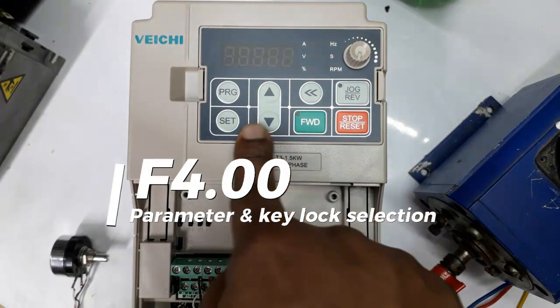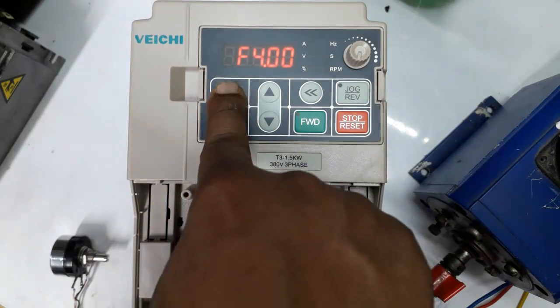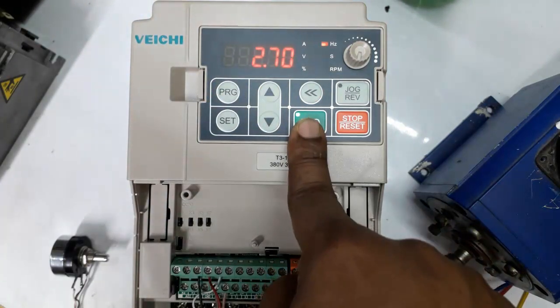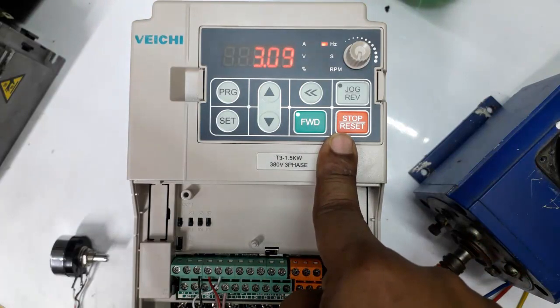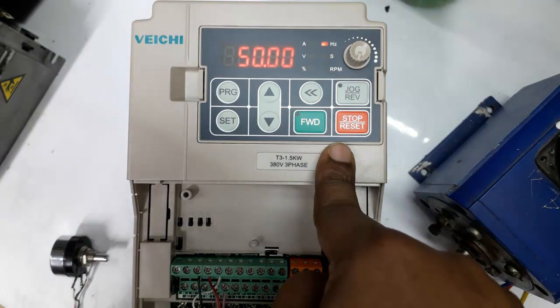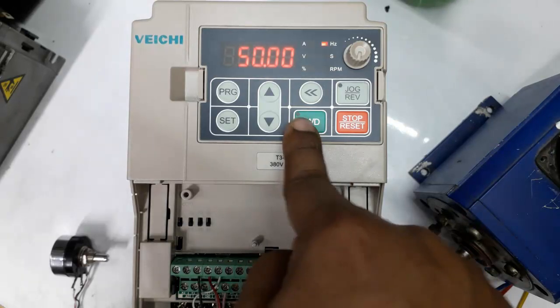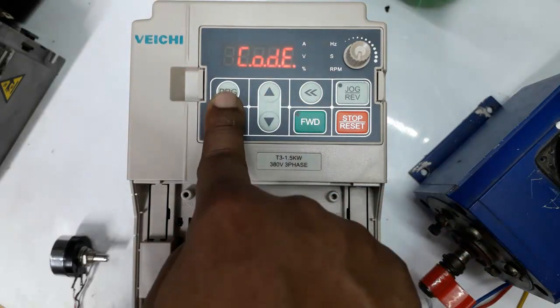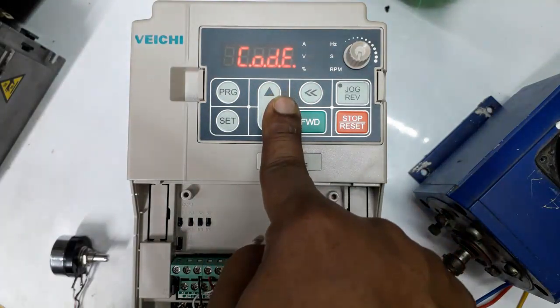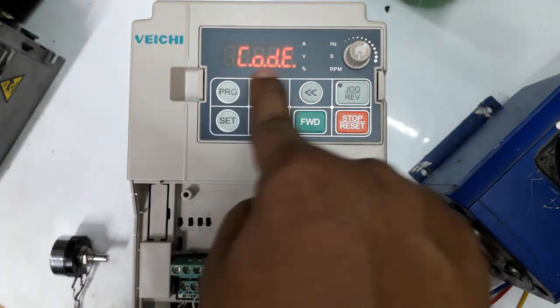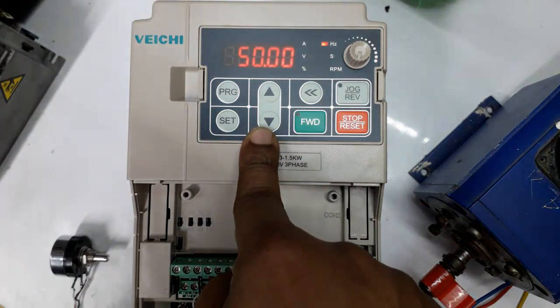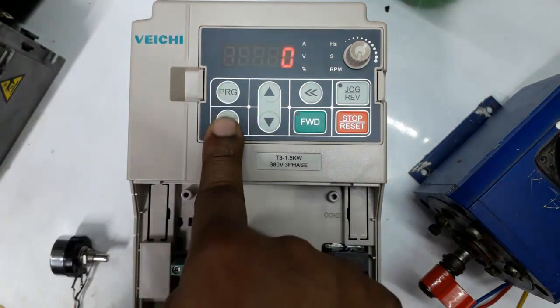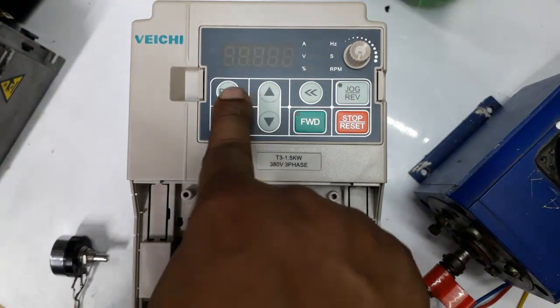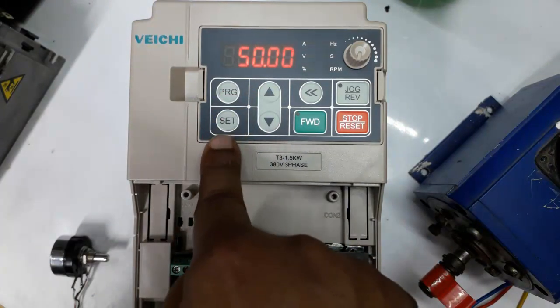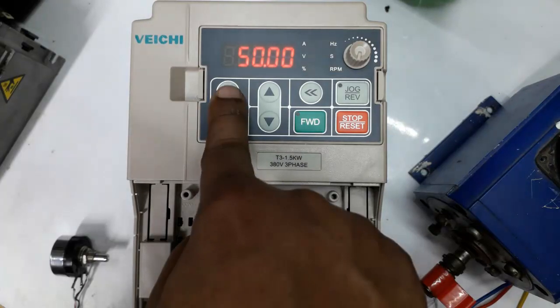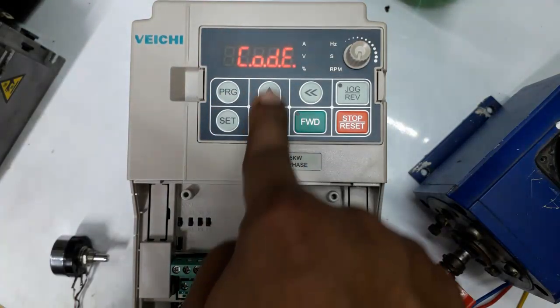If you set it here to 2, the drive keyboard or keypad is locked, only the forward and stop buttons will work, the other buttons do not work. You see, when we press program, it displays a code alarm. That means all buttons are locked except the forward and stop buttons. So if you want to program again or work by keyboard or keypad, you first need to unlock the drive.